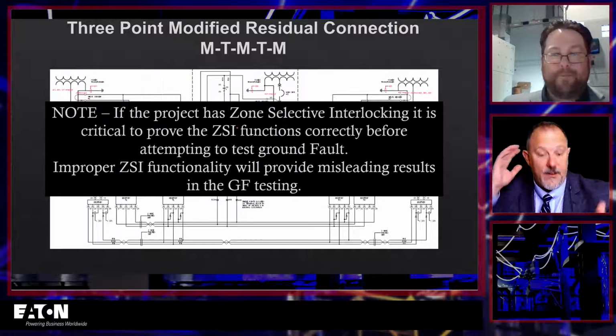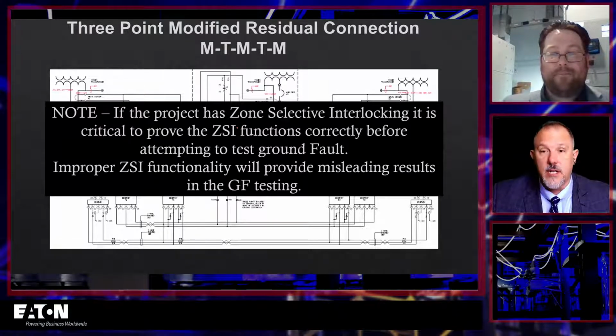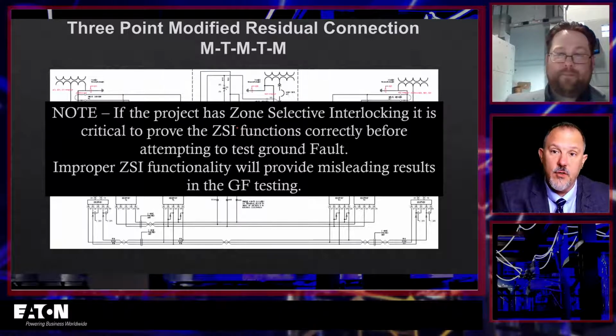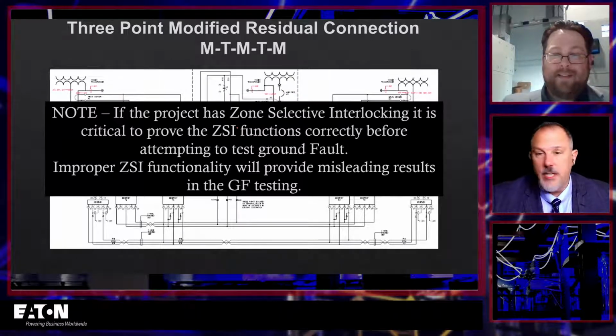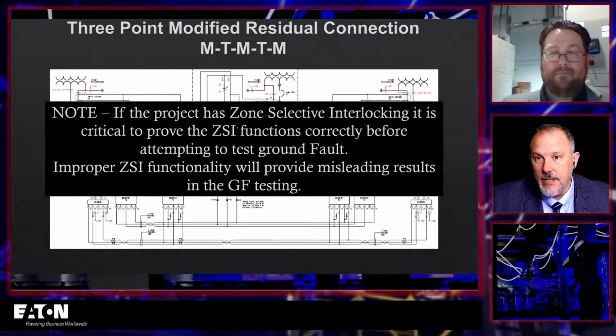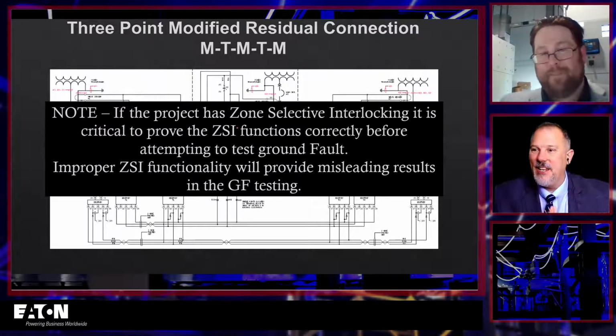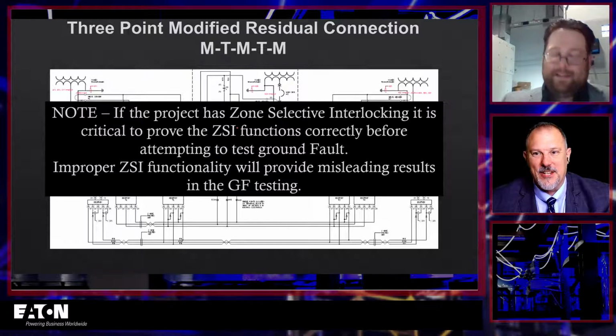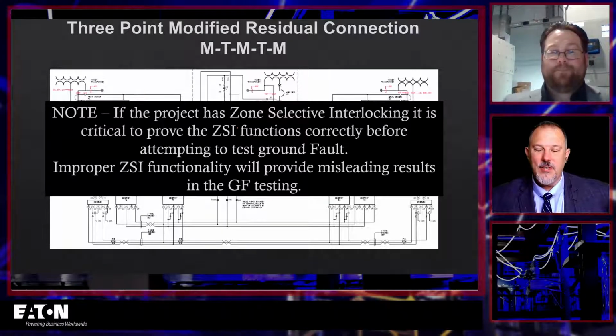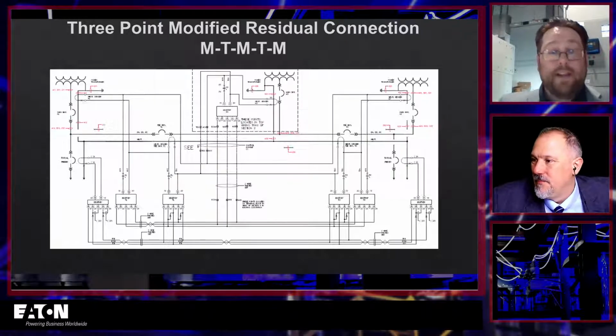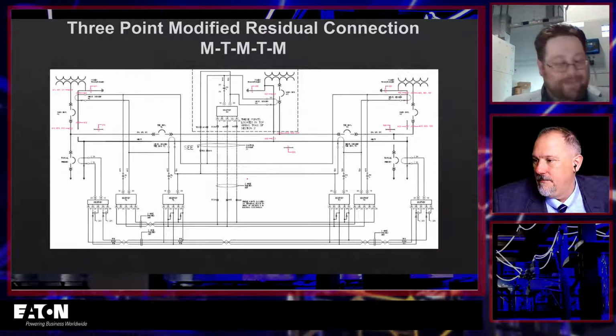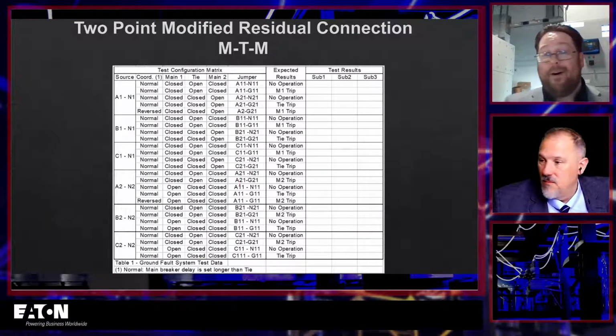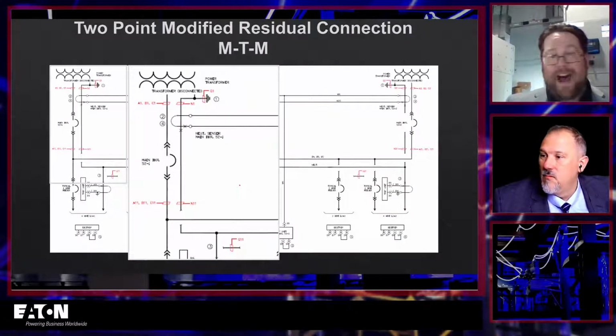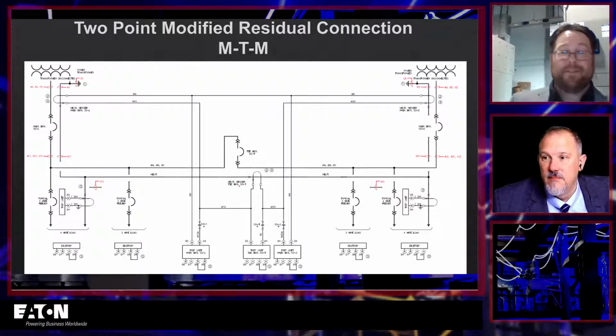And if you're going to test ZSI, for example in 240.87, if you're employing zone selective interlocking to meet the requirements of 240.87, you're already doing ground fault protection in here, and you know you have zone selective interlocking. You've got to make sure that's taken care of, because if you're testing the ground fault and you're actually tripping on zone selective interlocking because of how you've got it set up, it's confusing. It really is. As you stated earlier, it takes a qualified, knowledgeable person to understand all these various systems that are interacting and how to deal with them. How do you ensure you're tripping on the functions you want?